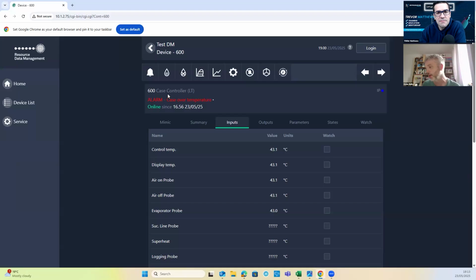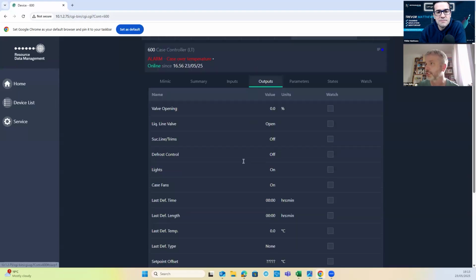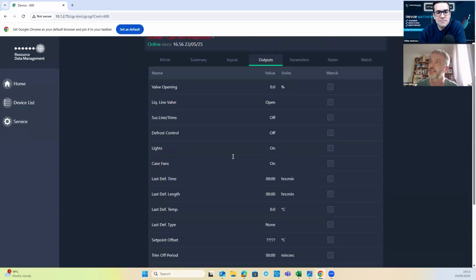So that will give you whether you are on a case, let's say, or a cold store. It will give you certain default options like, do I want fans on in defrost? Do I want a door switch? Just things like that. If you select the other options, which are for what we call a mobile controller, a self-contained cabinet, it will give you parameters for compressors. If you look down the parameter list for this controller, you'll see there's nothing in there for compressors because it thinks this is a piped case. And this is an electronic valve controller anyway. It wouldn't expect normally a mobile case to be an electronic valve.